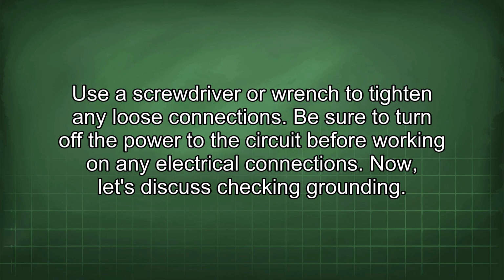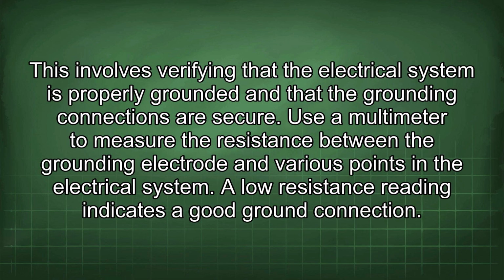Now let's discuss checking grounding. This involves verifying that the electrical system is properly grounded and that the grounding connections are secure. Use a multimeter to measure the resistance between the grounding electrode and various points in the electrical system. A low resistance reading indicates a good ground connection.